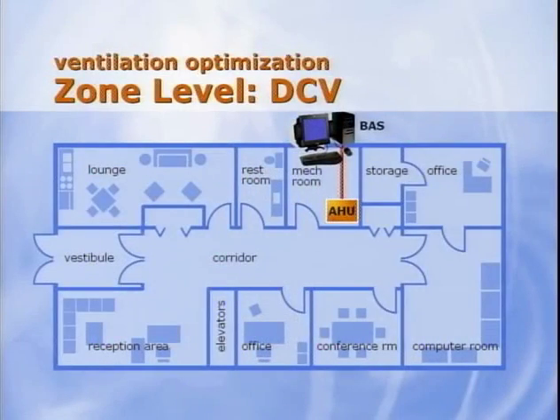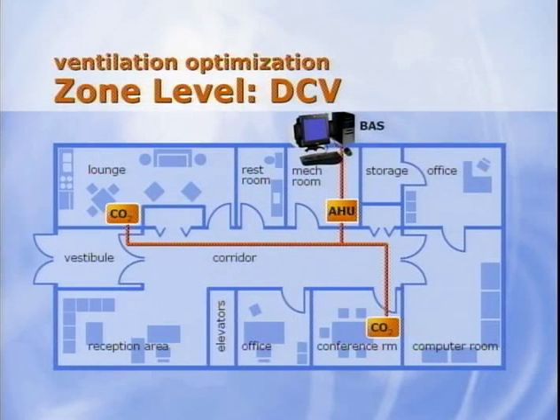In most rooftop VAV systems, the best approach often combines several demand control ventilation strategies at the zone level, using each where it best fits, and then couple these with ventilation reset at the system level. With this strategy, CO2 sensors are installed only in those zones that are densely occupied and experience widely varying population. In this example, CO2 sensors are installed only in the conference room and the lounge. These are good candidates for CO2 sensors and provide the most bang for the buck.